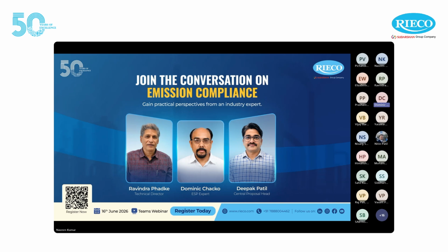And explaining back corona is a little complicated, and I don't think I can do it at this moment through this talk. But please understand that when back corona sets in, beyond a certain level, if you go on increasing the power to the ESP, the performance actually deteriorates. Rather than emission coming down, emission will go up after a certain threshold. So traditionally, this problem has been addressed by large OEMs like BHEL through a method called charge ratio charging. That is, the transformer rectifier panels will be operated in a mode called charge ratio mode. That is only a kind of compromise. You are just limiting the energy to the threshold level above which the problem is likely to happen.